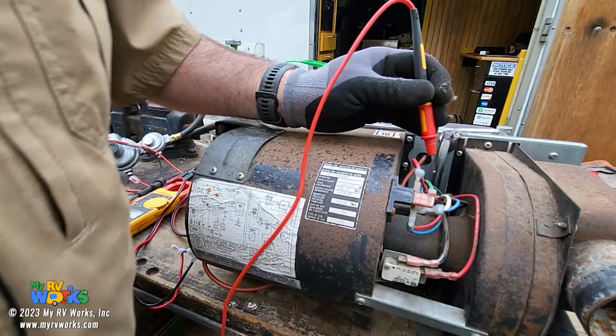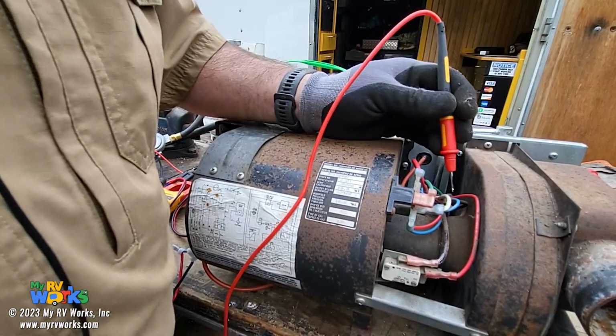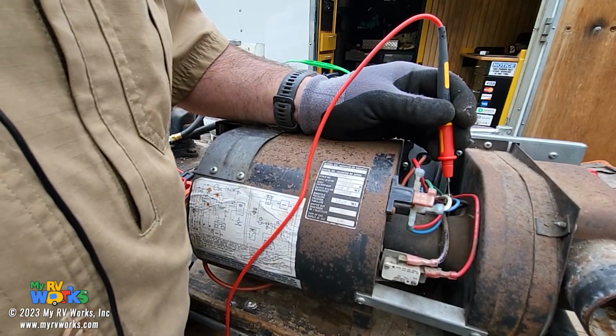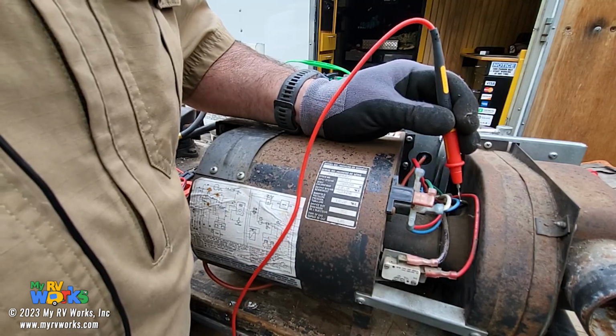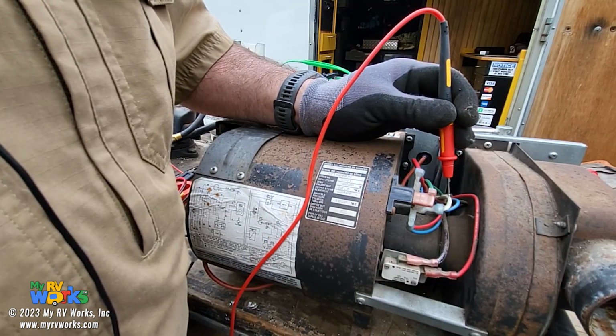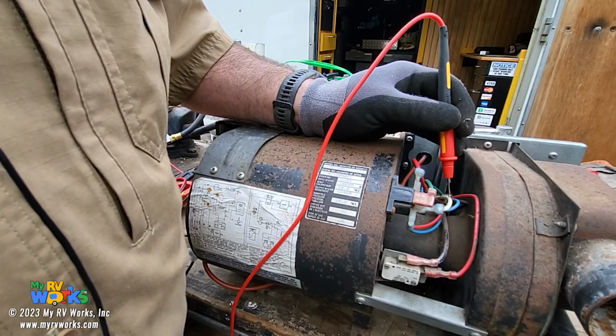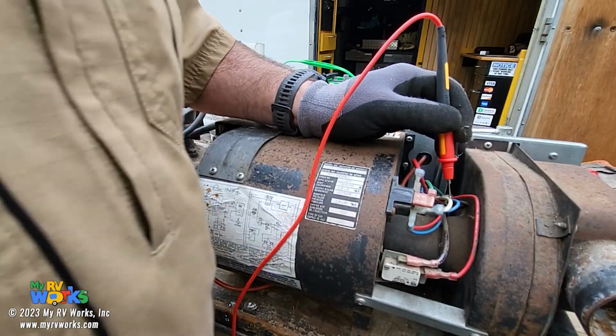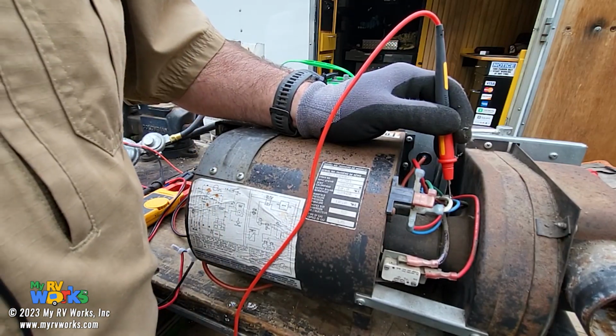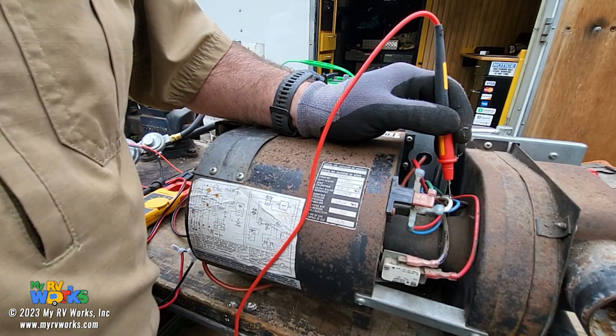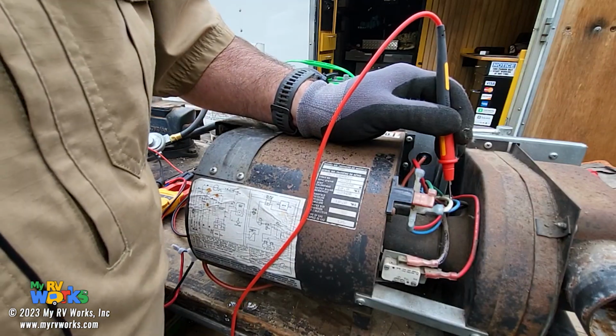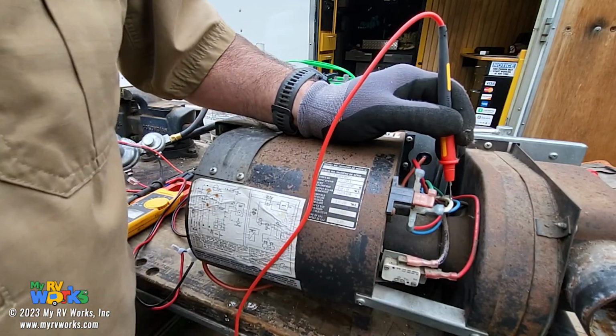I want to be careful how I explain this - I don't want to confuse people, but basically the call for heat signal came back on this blue wire, and it's going to go through several little stops along the way. Any one of those stops could open the gate and open the circuit, preventing the call for heat signal from getting there. The thermostat could be satisfied, the high temperature switch in the back could trip open, or here we have the sail switch.